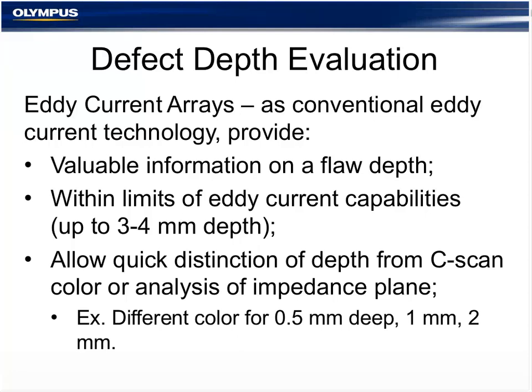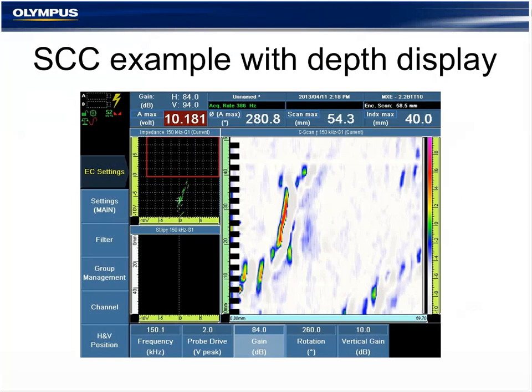Eddy current penetration really goes up to 2 to 4 millimeters. I wrote 3 to 4. That's typically the maximum reach of eddy current. So it's not fair to say that eddy current will be able to detect up to half an inch, at least not the eddy current we're talking about in this solution. The eddy current array has the advantage of allowing a very quick distinction of the defect depth from the C-scan color, or from analysis of the impedance plane if somebody wants to. It takes longer and you can get a more thorough analysis, but it's possible to do. So, for example, you can distinguish a 0.5 mm deep defect from a 1 mm or a 2 mm one, as they have different colors. And that's precisely what this example is showing right now.